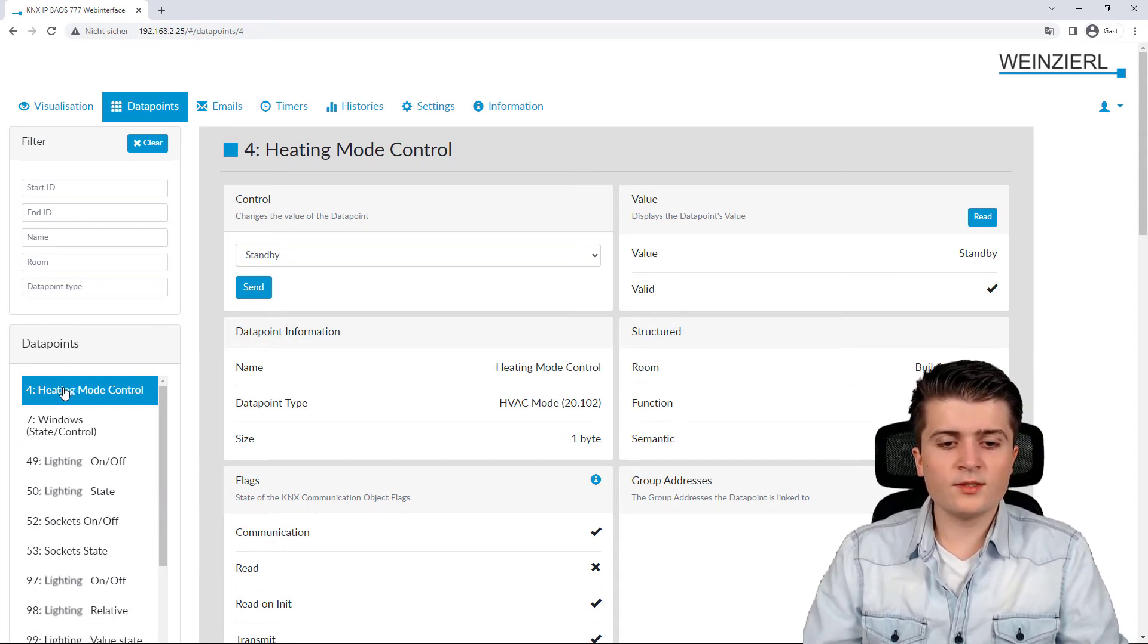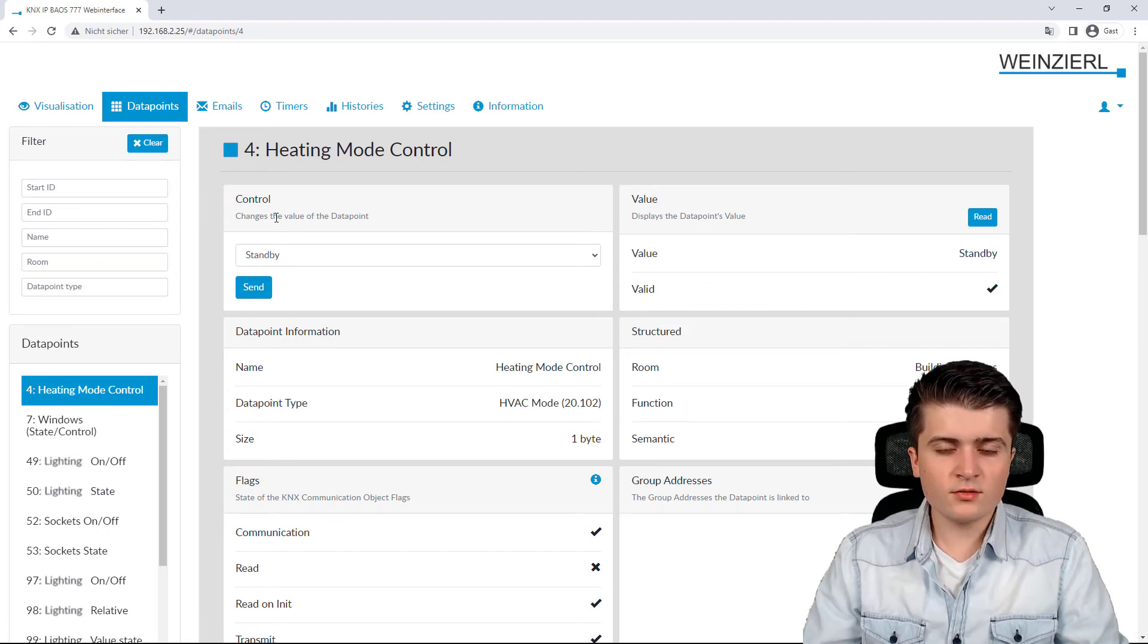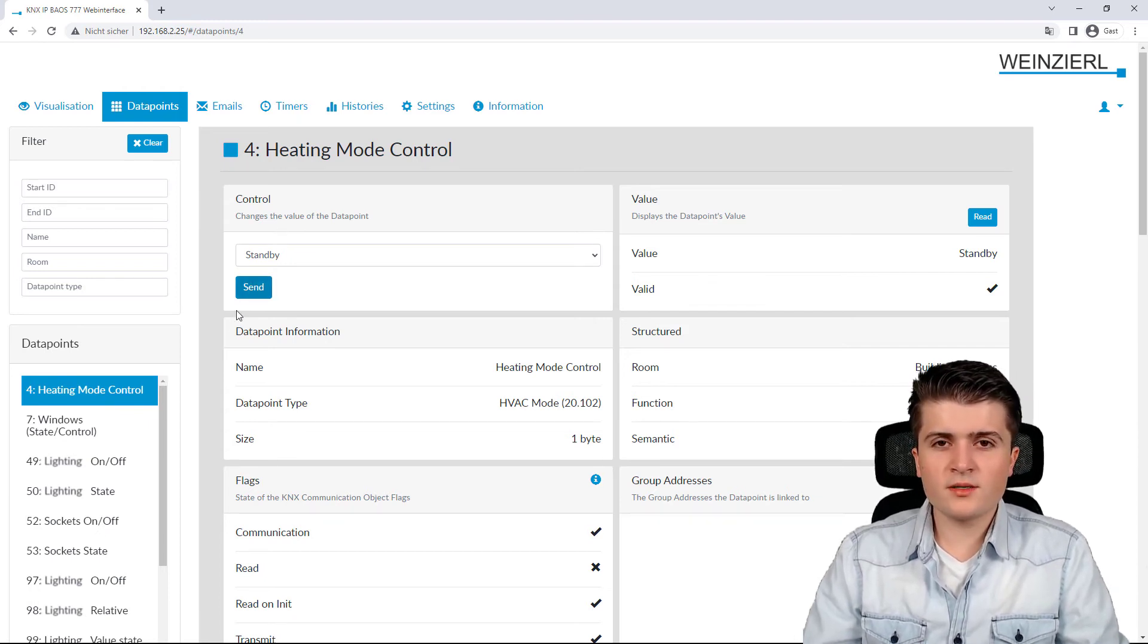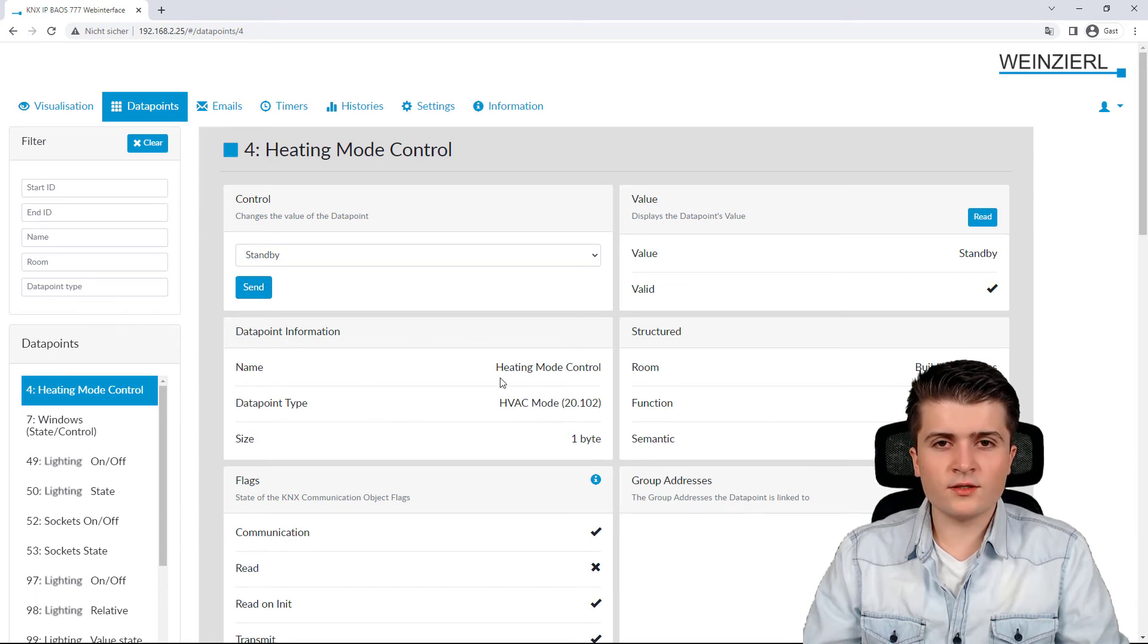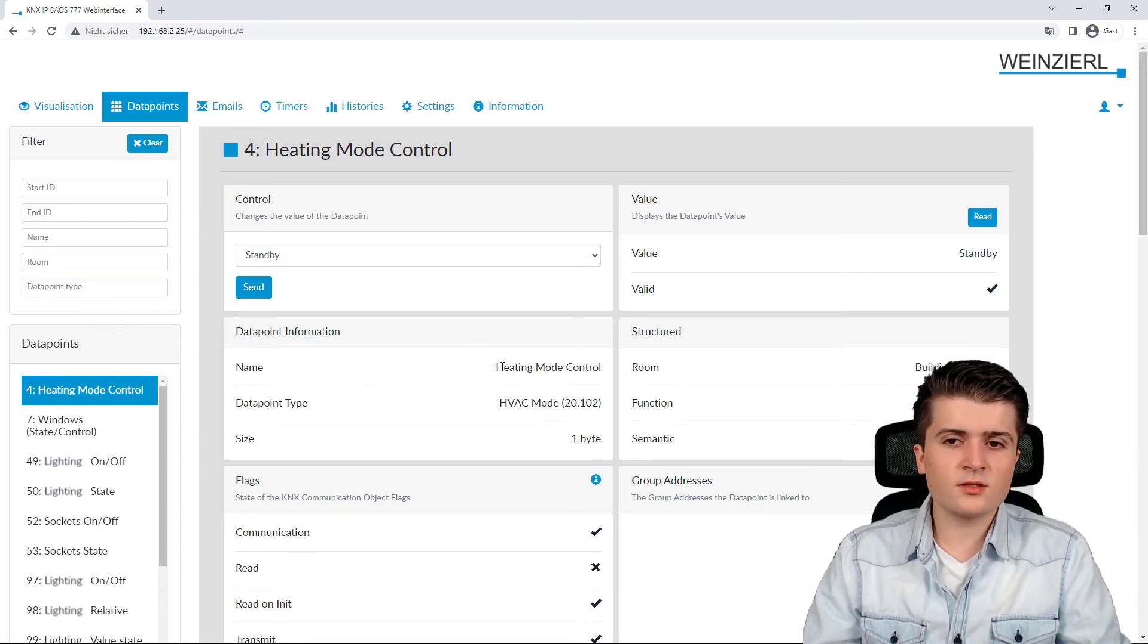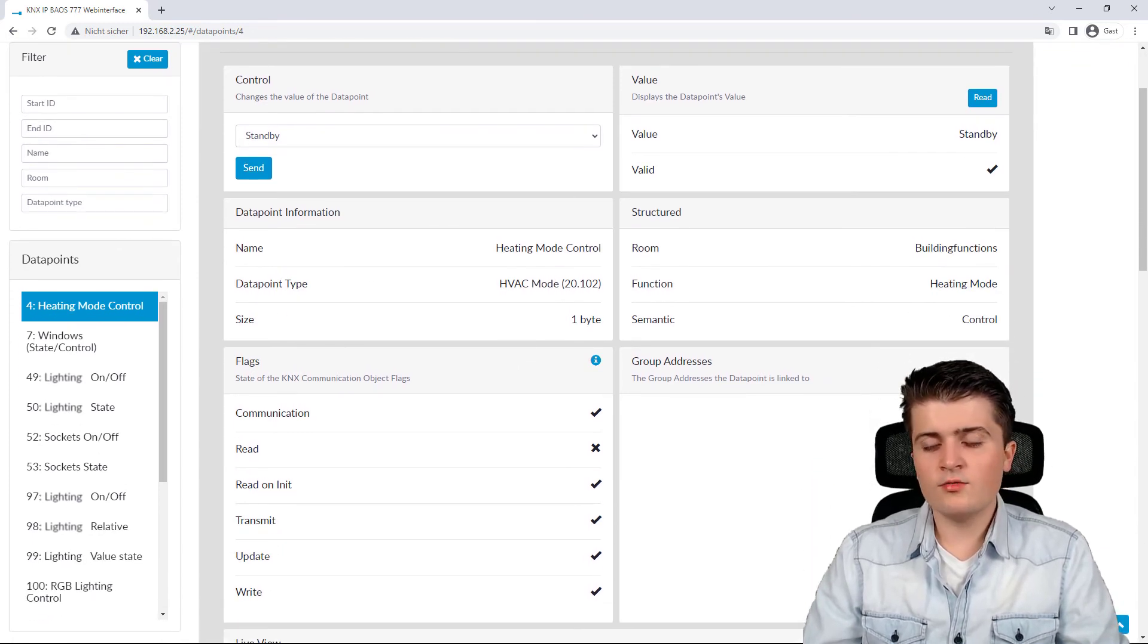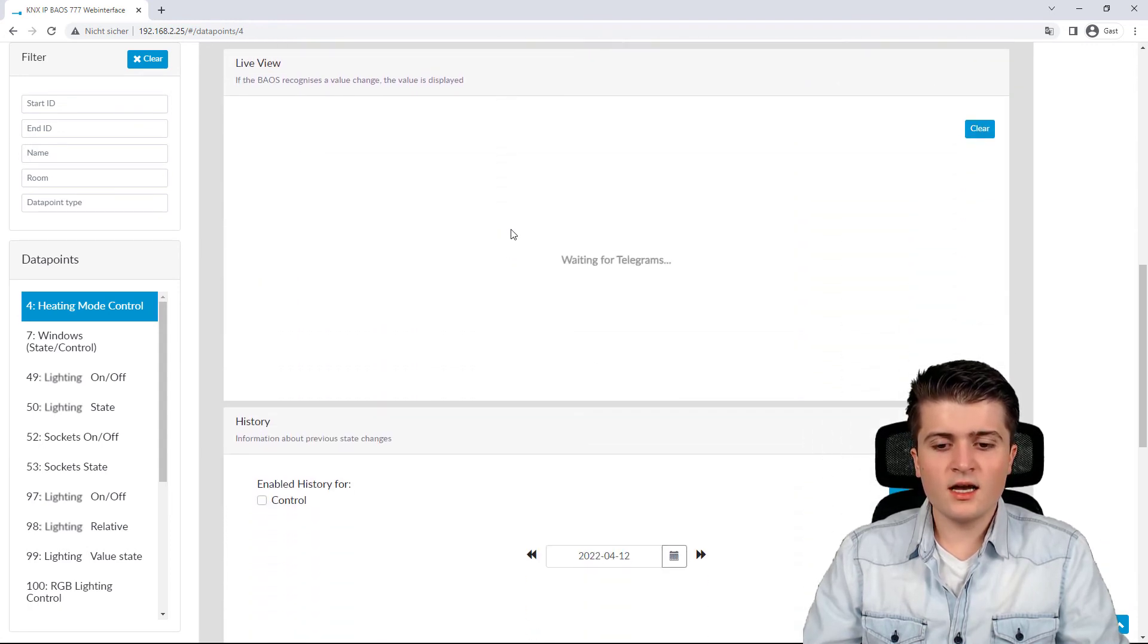So, here, for example, we have the datapoint for the heating mode control, or the group object. And here, we can also see the datapoint information, so which datapoint type it has. We can see the associated group addresses, as well as the flags.